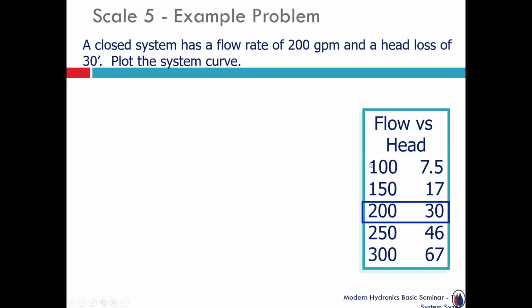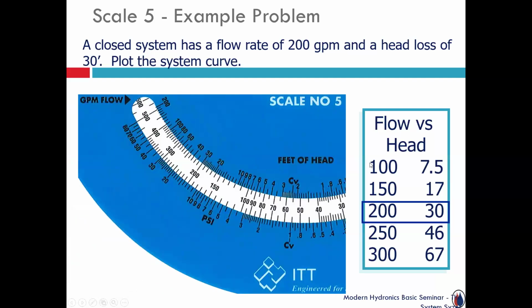Plot a system curve that has a flow rate of 200 gallons a minute and a head loss of 30 feet. So what we're saying here is, if I took that scale and said, hey, what are my known conditions? Start with this. You did a calculation and said, I need 200,000 BTUs. I need 200 gallons a minute, whatever the case may be. And in that system where I'm moving that required flow rate, I'm going to have a pressure drop of about 30 feet of head. So that's a known. That's accurate.